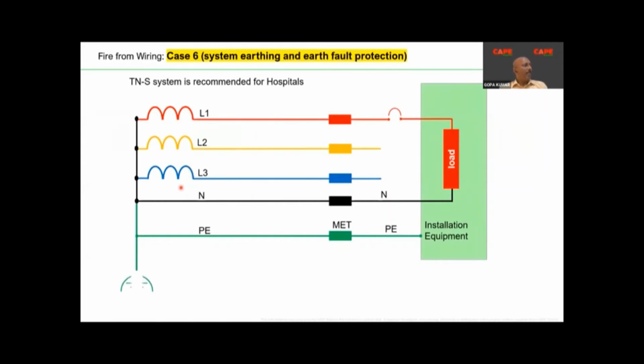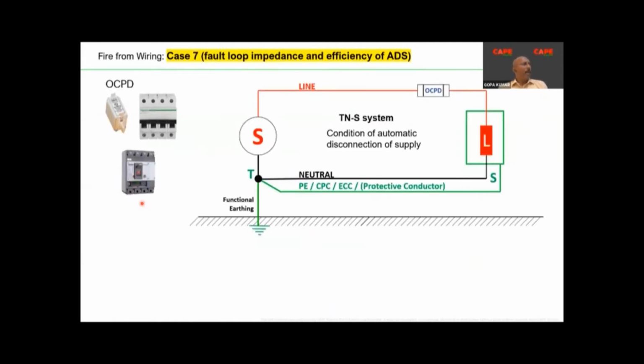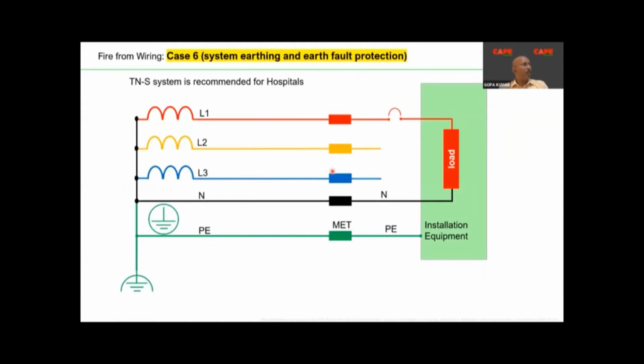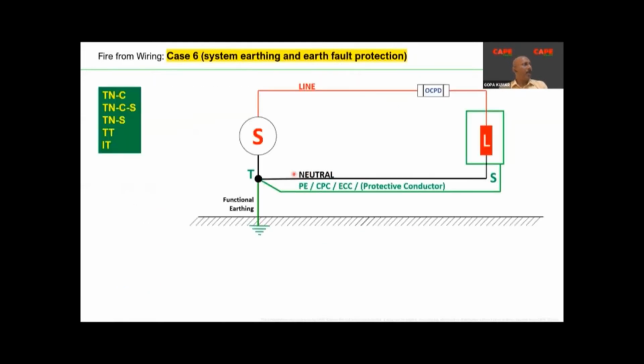So basically a three-phase network looks like this. What you should understand is that the metal body of your panel board is connected back to the neutral of the source through a metallic wire sufficiently sized to handle the fault current. If, instead of a TN-S network, you use a TN-C network in your building or hospital, you can be sure TN-C can catch fire. You are not supposed to use TN-C in your building.